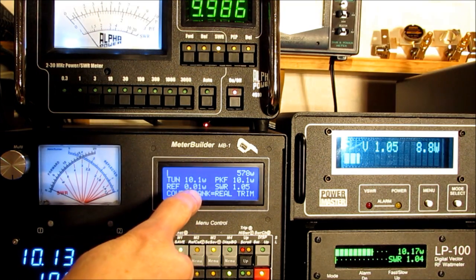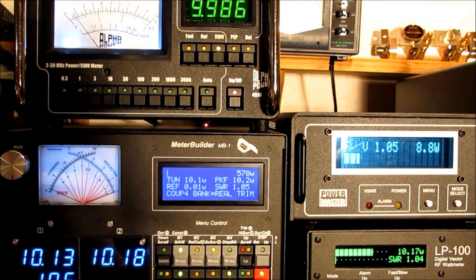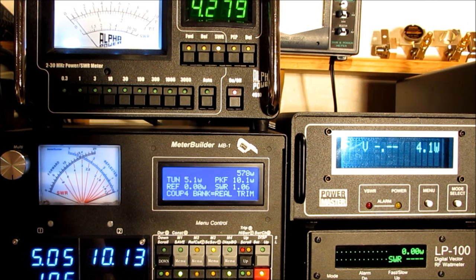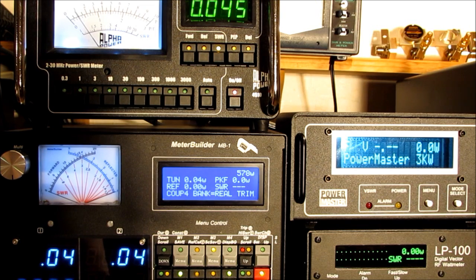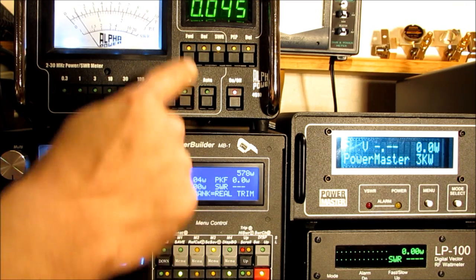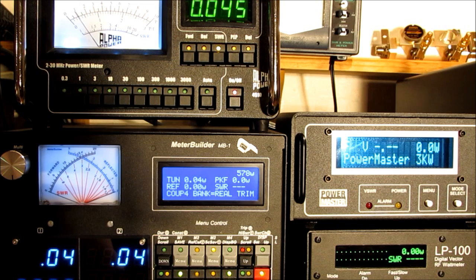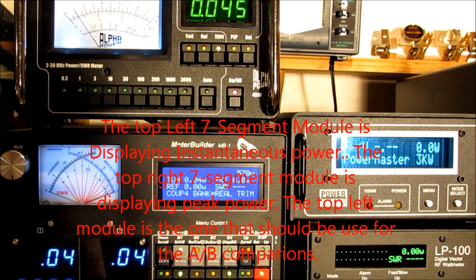Now remember, this meter was calibrated to this meter, and that's what we should see a fairly close match with. Let me go to the low end of the spectrum. Now, the PowerMaster cannot measure below 0.5 watts, and the LP100 starts at 50 milliwatts. So here, even at the very low power ranges, we're relatively close to the Alpha, 0.04 watts versus 0.045.